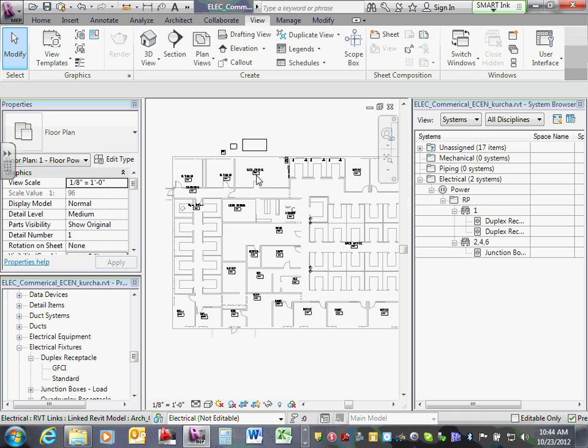This says: air handling unit located in the electrical mechanical room, 15 horsepower, 2.8, 3-phase, division 16 to provide VFD for unit. So Jeff, I need an air handling unit and a VFD right next to it. Can I have thumbs up, chat? How do I know? It says so. Let's go drop an air handling unit.